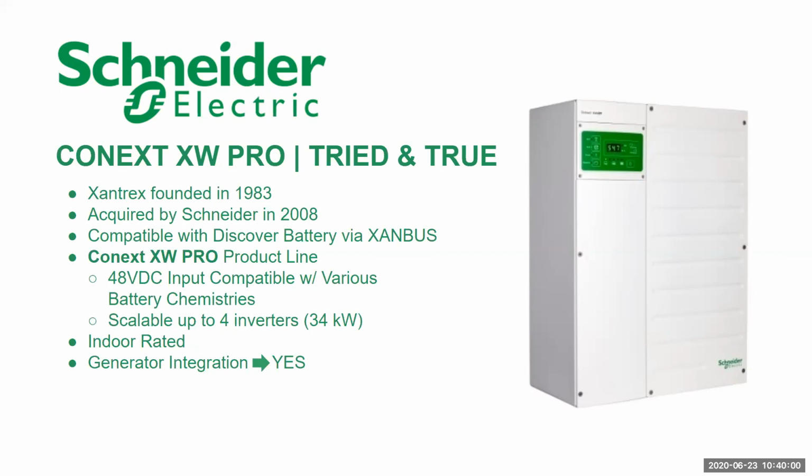Again, this is a 48-volt system, so you could do a Discover lithium battery, or you could do flooded. You can stack up to 4 inverters pretty simply, and in this case, you would use a power distribution panel. That's the equivalent of a load center for the XW line. Indoor rated, generator integration. I'm not including much warranty information on these because we're not referring to any batteries. The megawatt hour throughput is typically associated with the battery cycling rather than just the inverter, because I'm talking about the inverter line rather than a battery line, since you can compare many battery lines with any 48-volt configuration to the Schneider line.